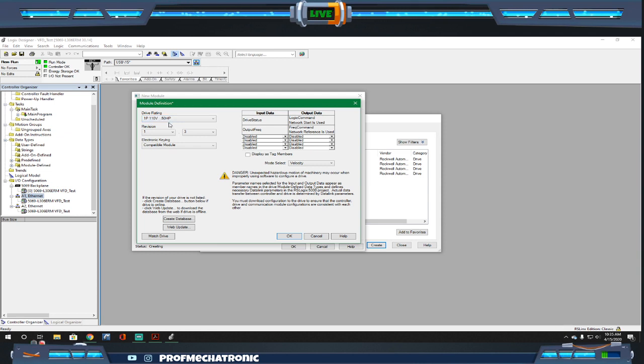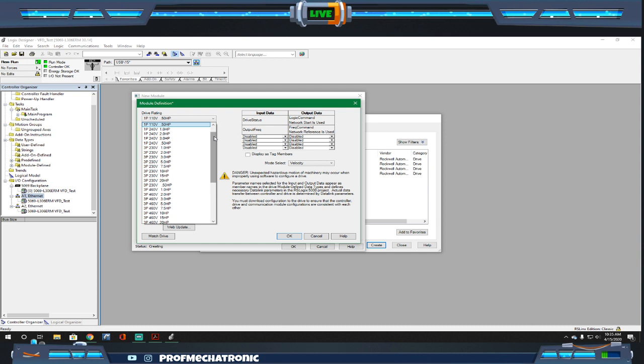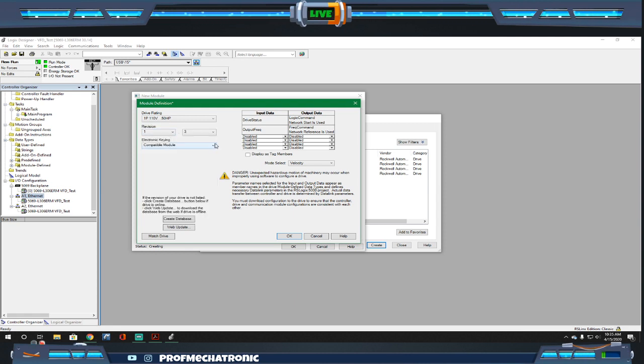Now, this is the proper drive rating for our drive, but more often than not, you're actually going to have to go in here and find the appropriate drive. So you can see there's tons of different drives in here. You've got single phase 1 horsepower, single phase 1.5 horsepower, all the way up to 3 phase 30 horsepower. So we can configure all of our drives in here. You've got 3 phase 600, 3 phase 460, all of those things can be set up in here. And then you have electronic keying. Do we need it to be an exact match, a compatible match, or disabled keying? So we're going to use compatible module because we just want to make sure that they're compatible, even if they're not exactly the same. This kind of allows us a little bit of flexibility.